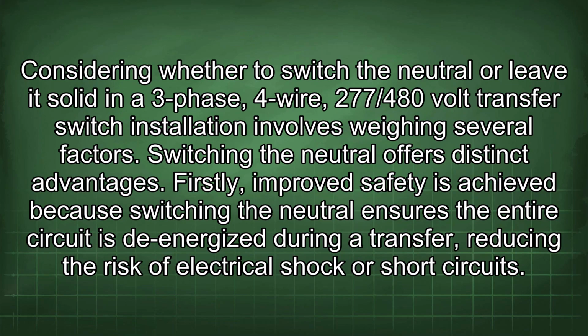Considering whether to switch the neutral or leave it solid in a 3-phase, 4-wire, 277/480 volt transfer switch installation involves weighing several factors. Switching the neutral offers distinct advantages. Firstly, improved safety is achieved because switching the neutral ensures the entire circuit is de-energized during a transfer, reducing the risk of electrical shock or short circuits.